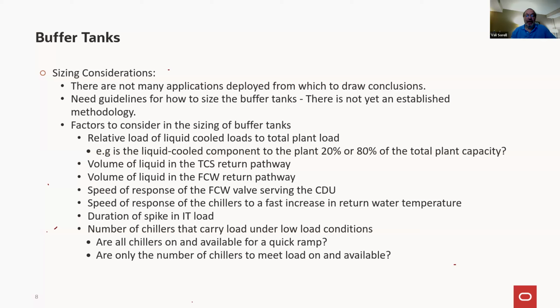Well, the thermal storage tank is passive, but you still have to have the control to it to recharge it when you've consumed the charge. So with a buffer tank, from the standpoint of design, it's like the simplest of all things. It's just the thermal mass. But the calculation of that size requires that you understand the performance of valves, chillers, and flows, and even the IT equipment. So it is a complex calculation, and there's a lot of consideration that needs to go into it.